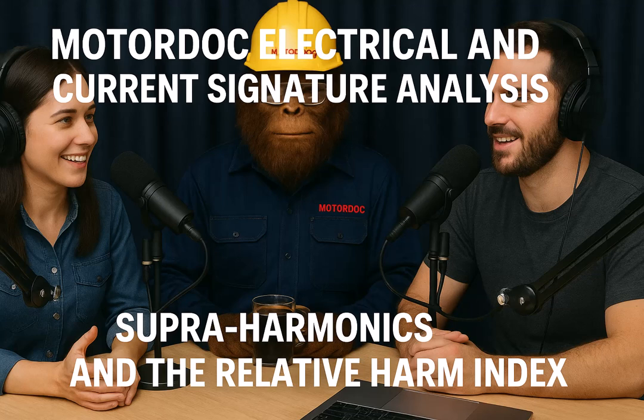Why the new focus? I thought total harmonic distortion, THD, already covered harmonics. Common misconception. Traditional THD usually only counts harmonics up to the 50th harmonic. For a 60 Hz system, that's only 3 kilohertz. Oh, right. Supraharmonics start at 2 kilohertz and go way beyond that 3 kilohertz limit. So standard THD measurements often completely miss the potential trouble these higher frequencies can cause. As systems get more complex with VFDs and such, we're just seeing more of this high-frequency noise.